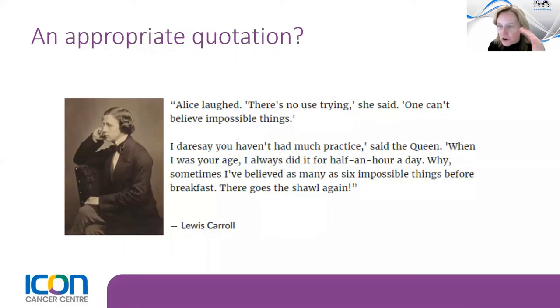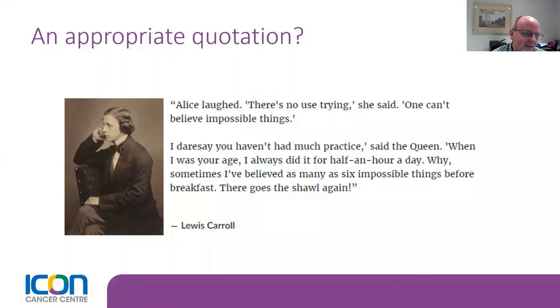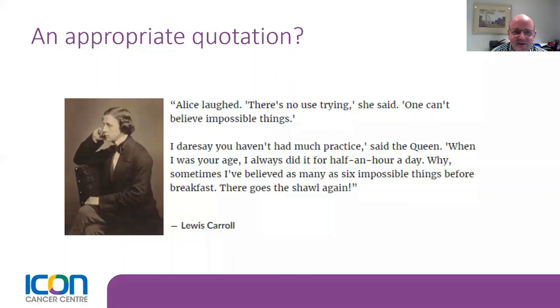If a department wants to do an SRS audit, is there protocol documentation for end-to-end testing? An end-to-end audit should follow your clinical process. You want to use an anthropomorphic phantom because it's very difficult to follow your clinical process including image matching without something that looks like what you're going to treat. There are a number of phantoms designed for SRS. You take the phantom through the process you've designed for patients — and that won't be the same in each department.